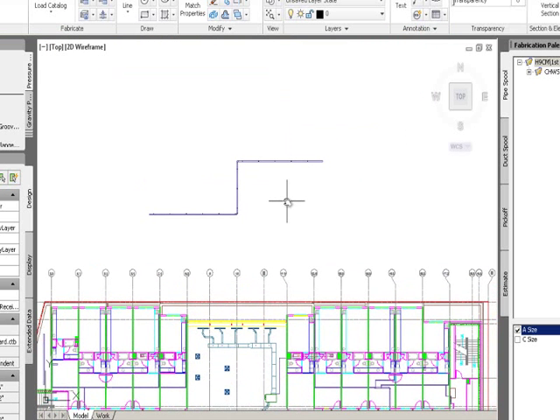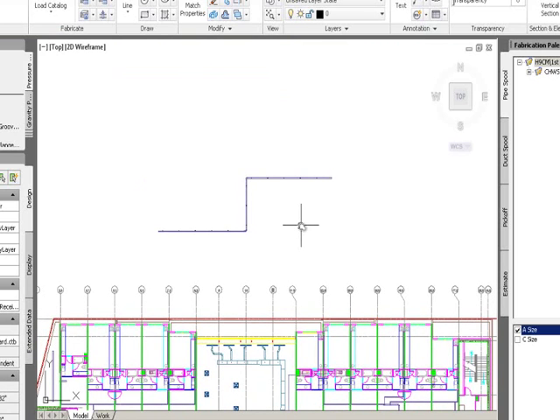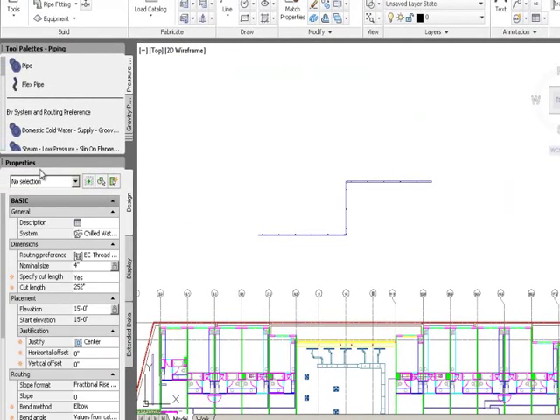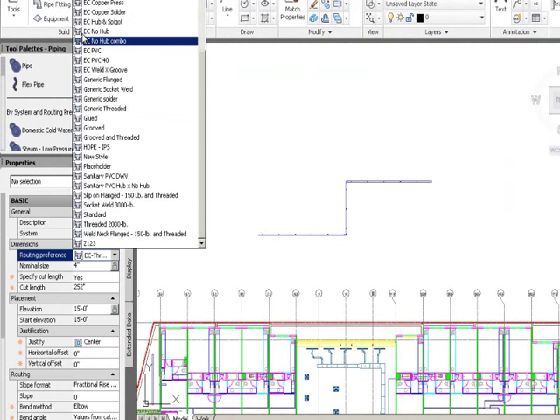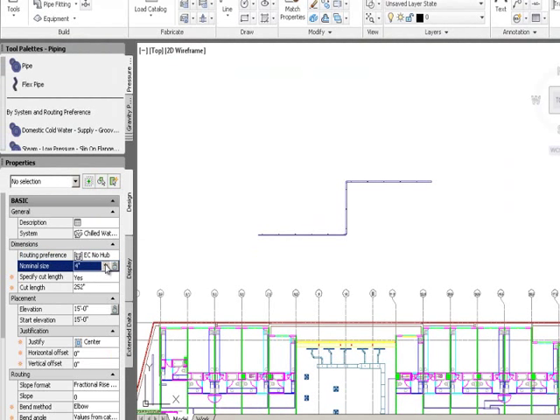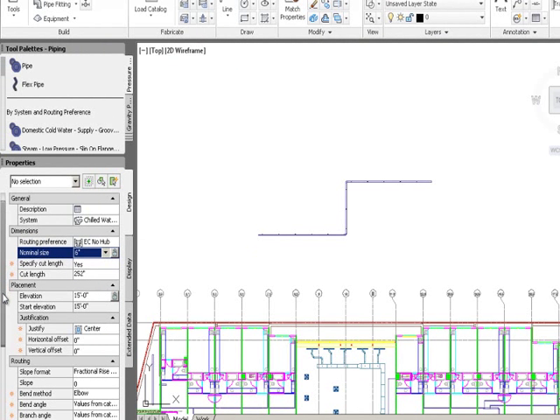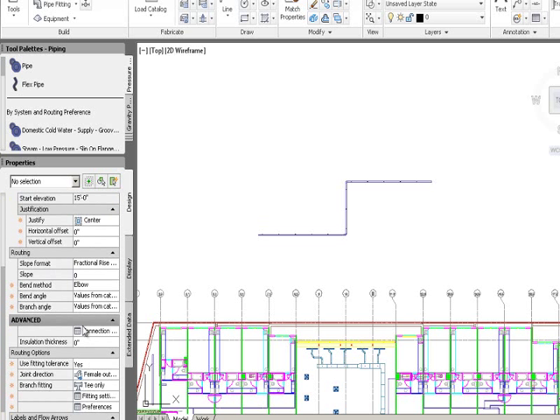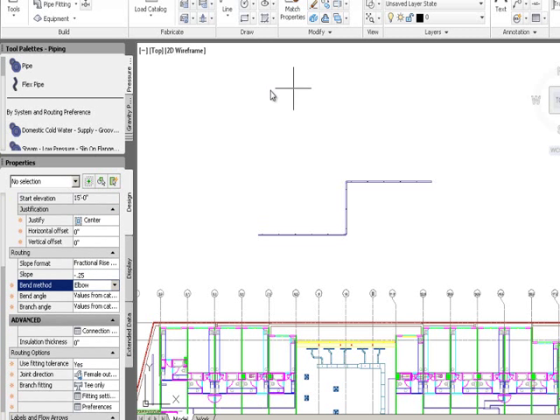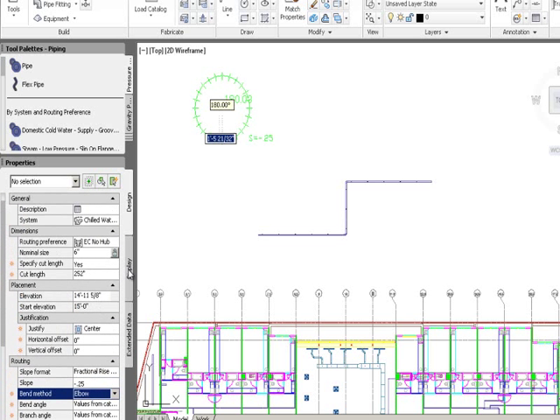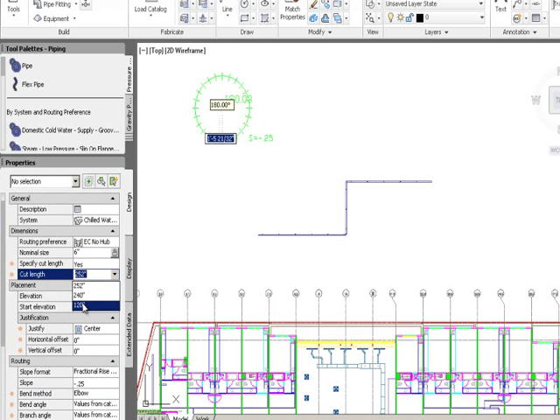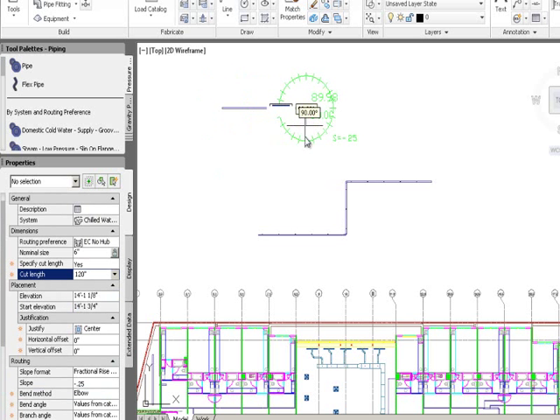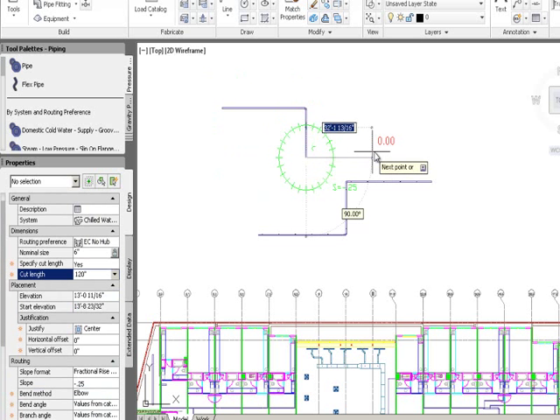Now I want to run some gravity sloped pipe. I change the routing preference to No Hub, run six-inch pipe at the same elevation, but this time add a negative quarter-inch slope. I also set it to automatically break the pipe into ten-foot sections as I run it.